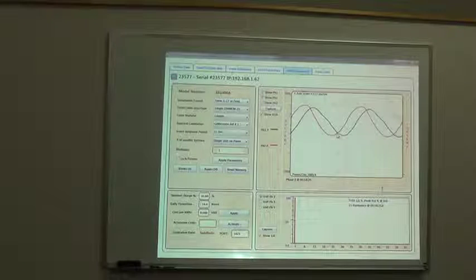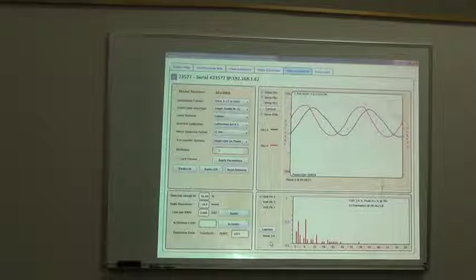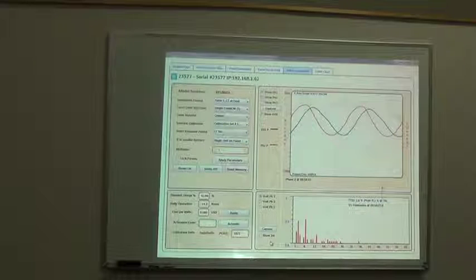So that's one easy way to estimate your savings based on the negative energy, because it's quite a bit of it. Now, for some states and some power companies, that value is a lot less. Some places in New Jersey, it's huge. It's 25% of the entire billing. When you have 25% of the entire billing in one thing, and you're saving 15% of that, by itself it becomes 60% of your saving. In Florida, it's about 28%.